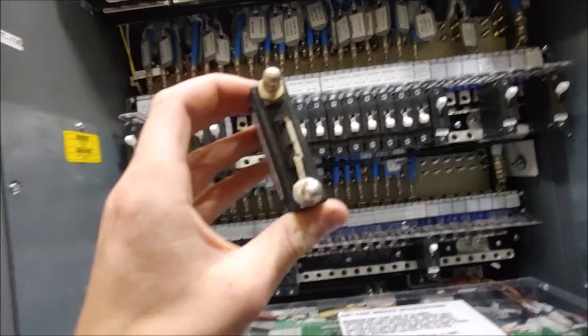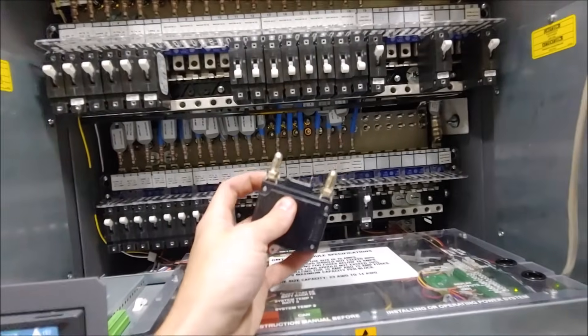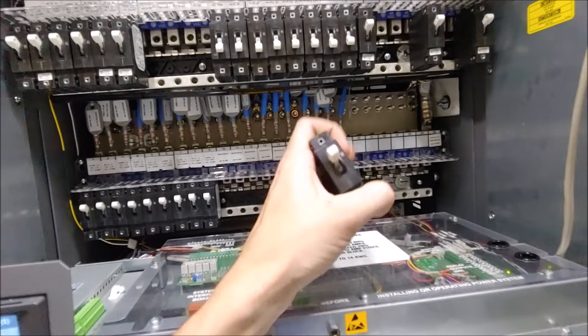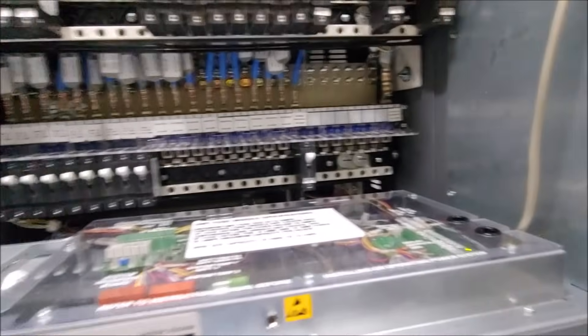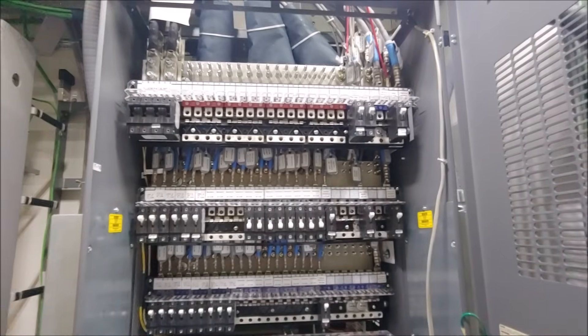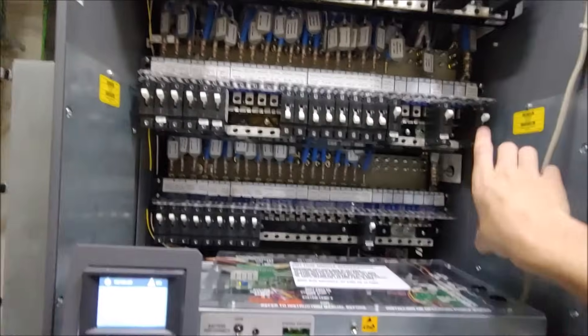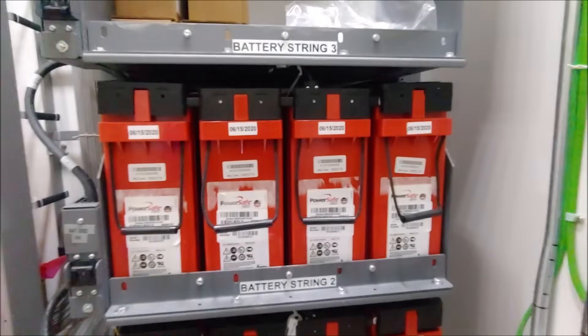These are DC breakers — they're different from AC because DC has little bullets on the back, called bullet breakers for obvious reasons. You can see how they almost look like a bullet. This one is about a 30-amp breaker. All of our LTE equipment up top is on these bus bars. This is our 24-volt DC bus bar, and these are both our negative 48-volt reverse-polarity bus bars.